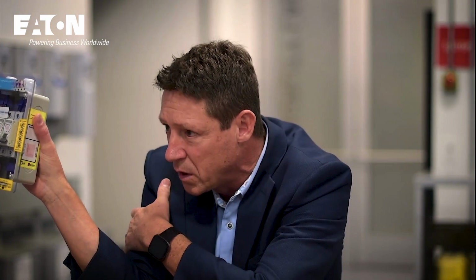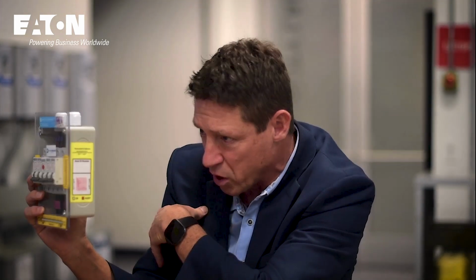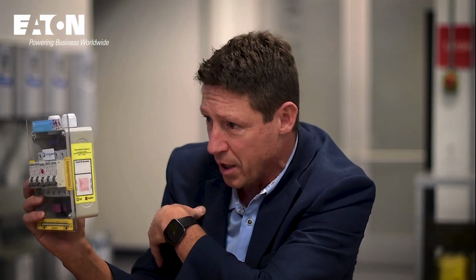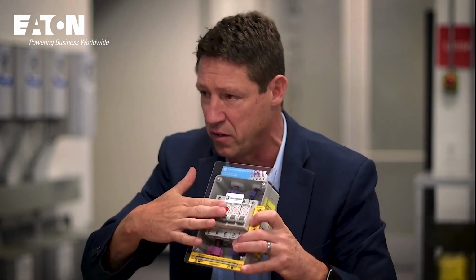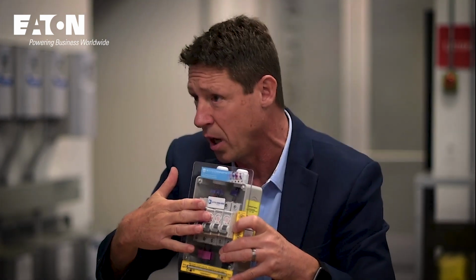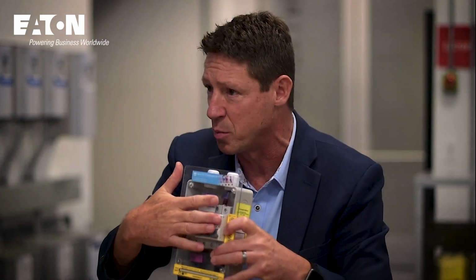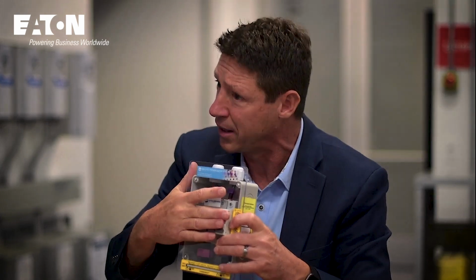Why? I had just moved into a house in Florida and did a thermography scan on my load center, because I can. What did I discover? I had a warm, almost hot, 2-pole 30 amp breaker. I went over and touched the face of the breaker - because I can, there's nothing preventing that - and I immediately felt that it was a warm breaker.